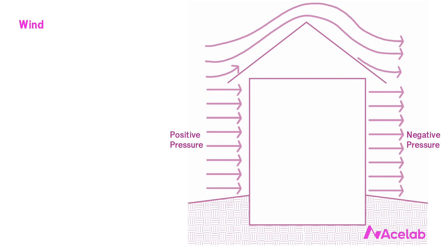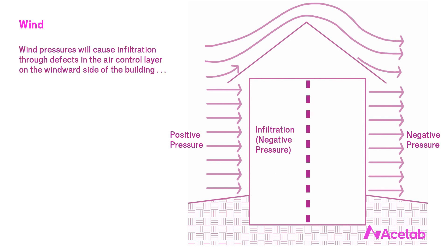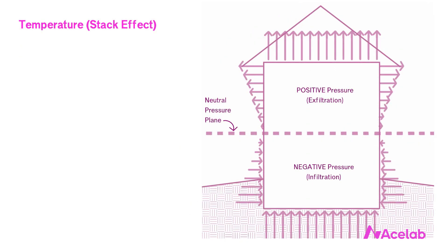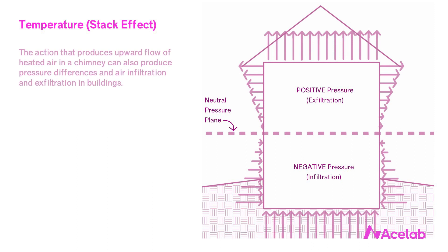With respect to wind, we'll see positive pressures on the windward side of the building and negative pressures on the leeward side. Wind pressures will cause infiltration through defects in the air control layer on the windward side and exfiltration through defects on the leeward side. Temperature will also induce pressure differences in buildings. The action that produces the upward flow of heated air in a chimney can also produce pressure differences and air infiltration and exfiltration in buildings. The concept of warm air rising is a pretty helpful simplification of what's going on.